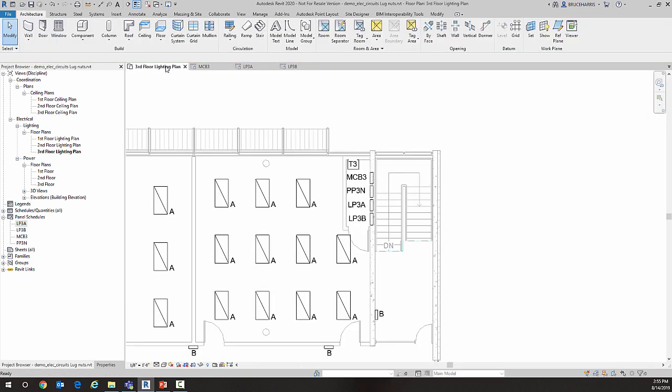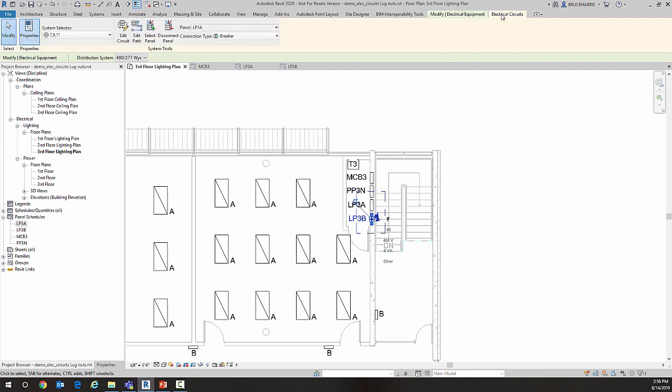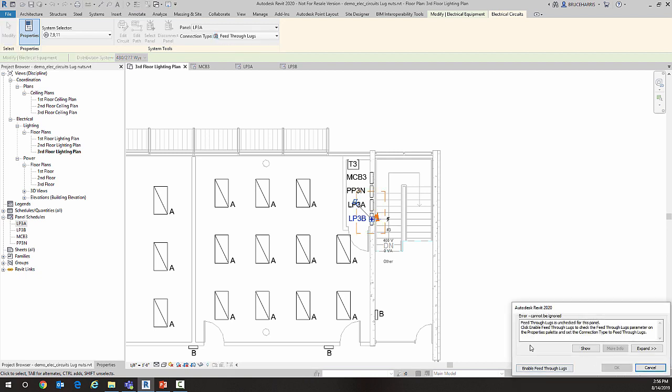Historically, that's the way we've been able to connect two panels. Now I'm going to show you a new method. I'll go back to LP3B and into the Electrical Circuits tab at the top. This time I'm going to change the connector type. This was not available prior to Revit 2020. I'm going to change it to feed-through lugs, and it gives me a message asking if I want to enable it.